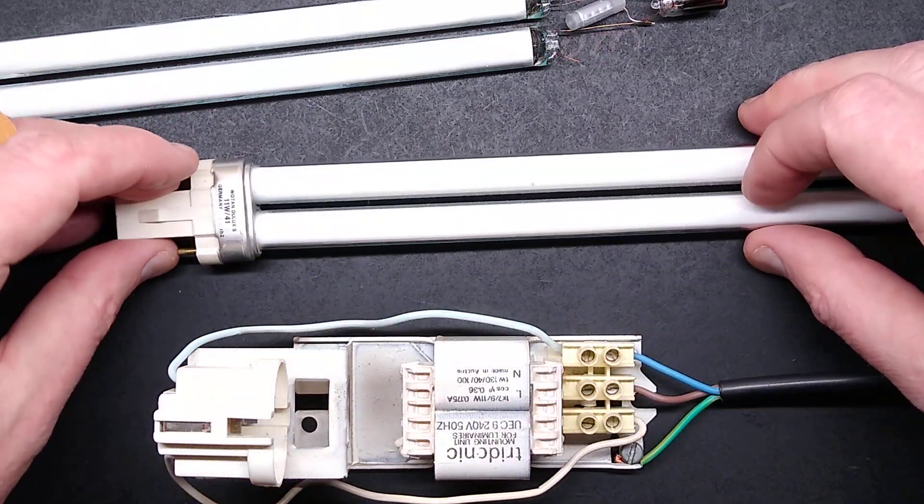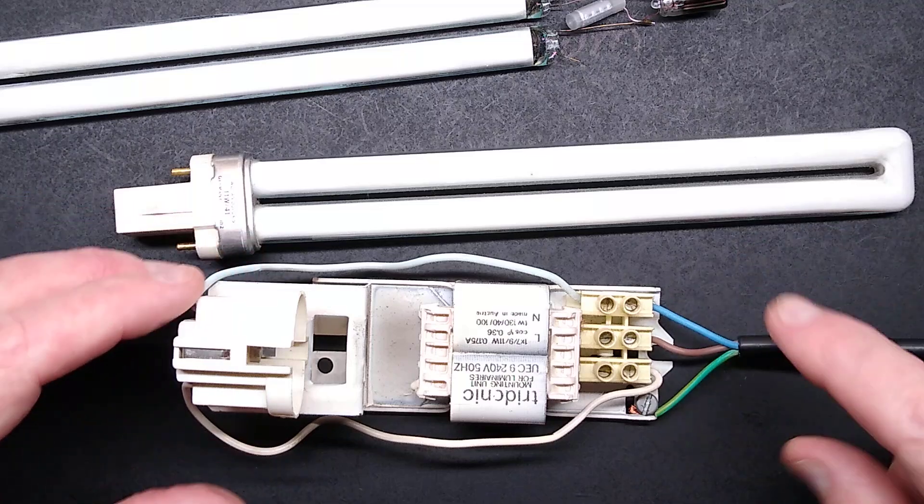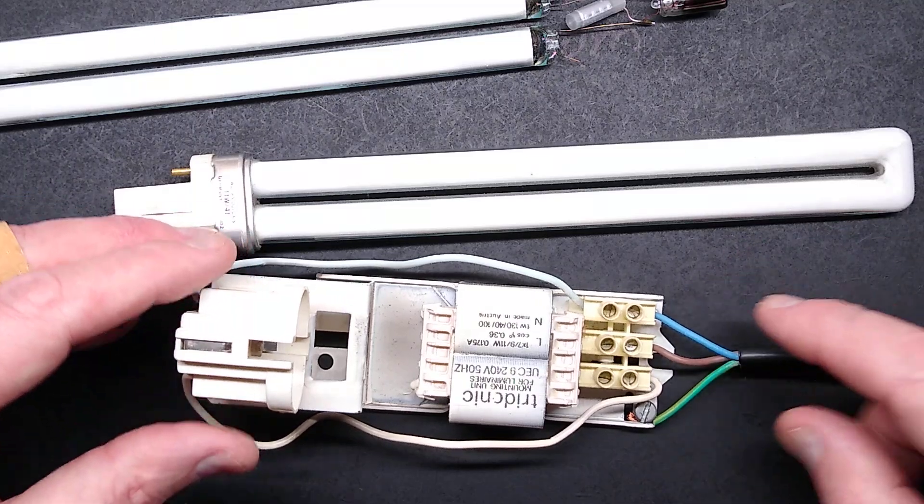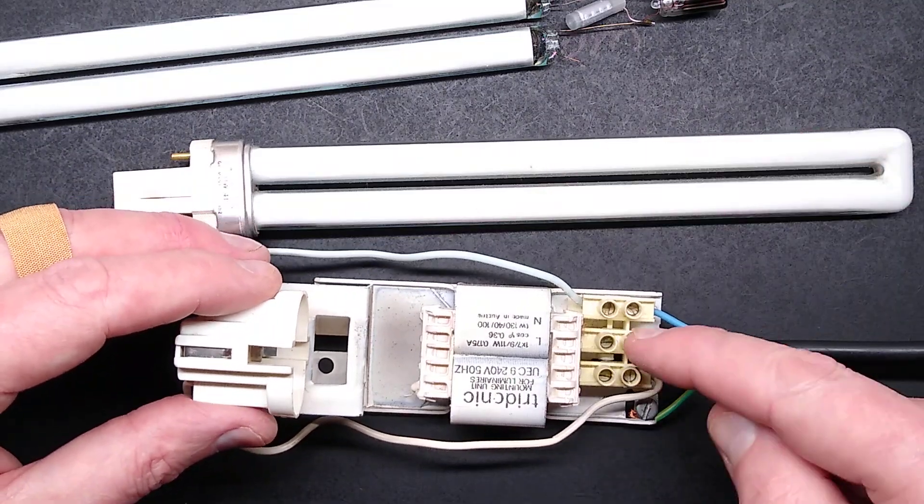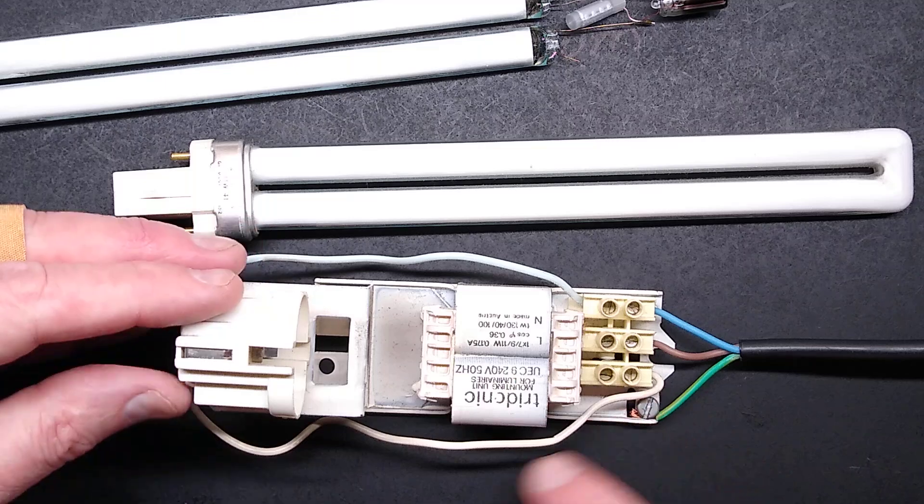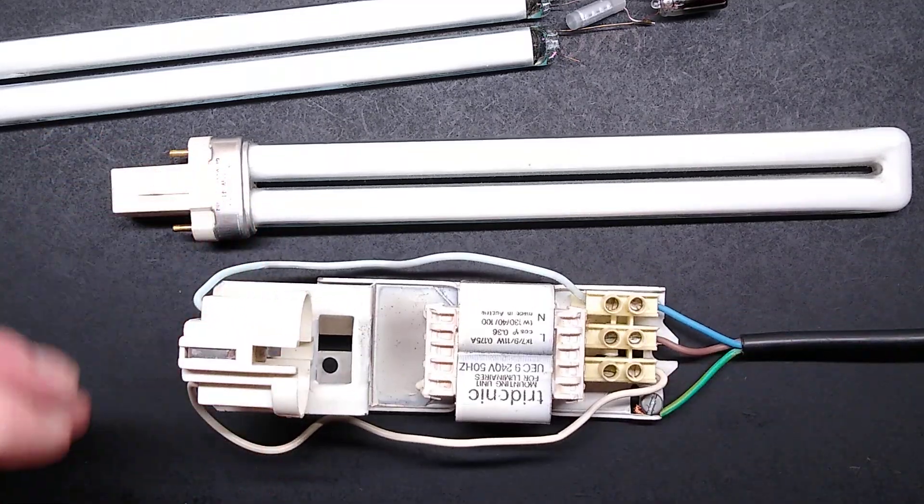This is the lamp with the starter built in, and this is just a simple inductor. It's got live, neutral, and earth. The neutral goes straight to the lamp, the live goes through the inductor and comes back out to the other end of the lamp, and the earth just goes onto the chassis.